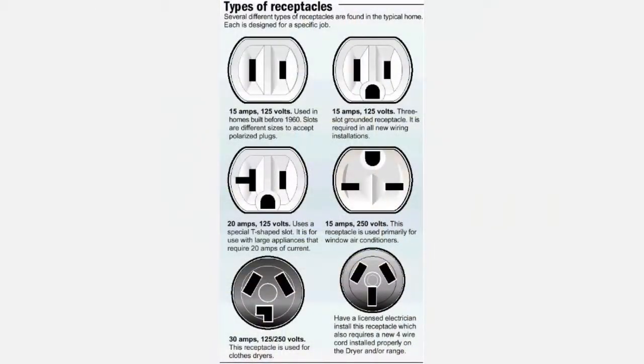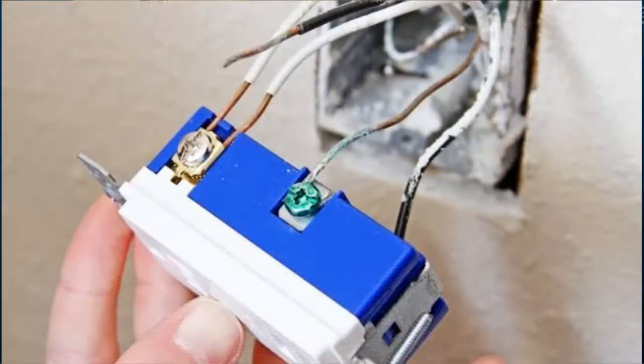And I guess with the type of plugs where you have a bare wire, you slide in a slot and a bayonet grabs it, if that hasn't been put in properly, it can rattle its way out, right? Well, yeah, that's what we call the quick click. At one point, they came out onto our market in the industry, and everything was built for speed. They were throwing up houses left and right, and everything was built for speed with these quick clicks. Our guys, we don't do that. We use the set screws on the side. We actually torque down the screws, and we don't get too many callbacks from our workmanship.